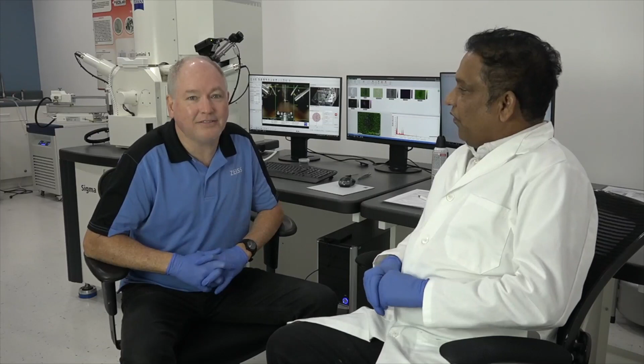Well, please share your experience when you were sent by Zeiss here to do a site survey to find out the suitability of this microscope to be installed in this laboratory. Thank you very much for the opportunity to come down here. I came down here the first time three months ago to check out the room by doing a site survey. With that, we checked the audio, the vibration, the harmonics, the temperature, the humidity, and we decided this is the perfect room to have the SEM after a few modifications.